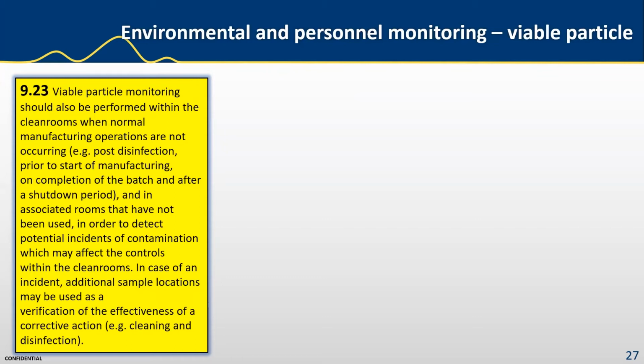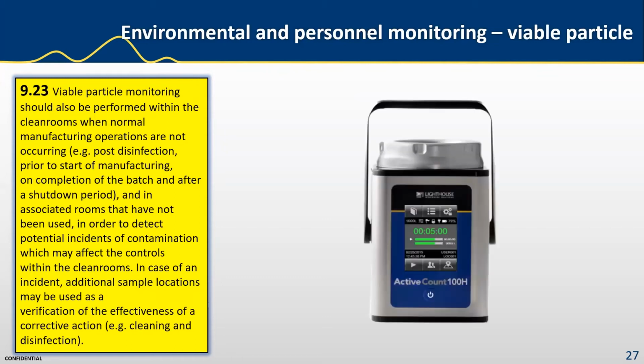cleaning and disinfection. So, we talk about portable air samplers are very effective in this criteria, and they should be used for this type of monitoring. And I would recommend that the selection of this type of air sampler should be considered in the context of ISO 14698, which has been shelved, and the more current standard is EN 17141. There is a new ISO standard under draft at the moment. It's not completed, and I believe that is ISO 14644 Part 20, which replaces the ISO 14698. I highly recommend that you check out these standards.